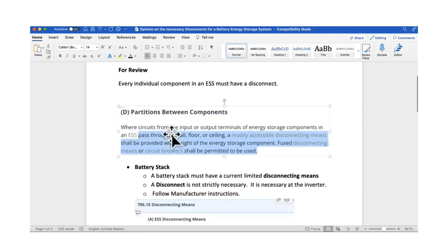Here is Article 706, 2020 NEC. And so it says partitions between components when we were looking for the disconnecting means. In Article 706, it says where circuits from the input or output terminals of an energy storage system components pass through a wall, floor, or ceiling, a readily accessible disconnecting means shall be provided within sight of the energy storage component. Fused disconnecting means or circuit breakers shall be permitted.